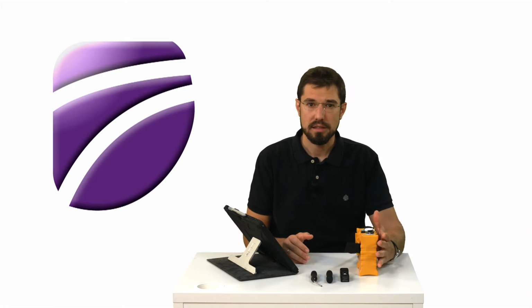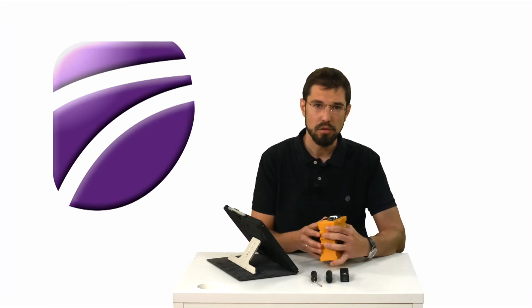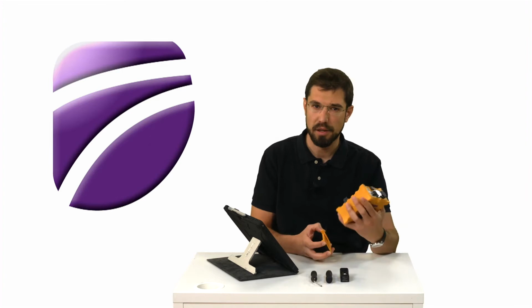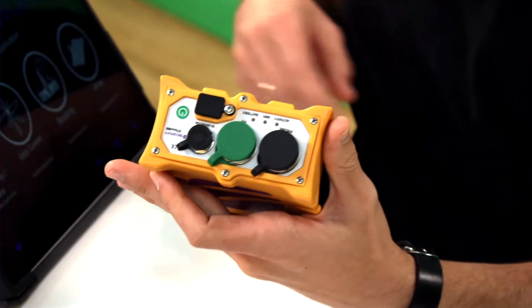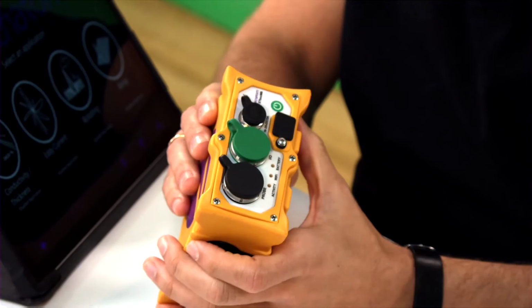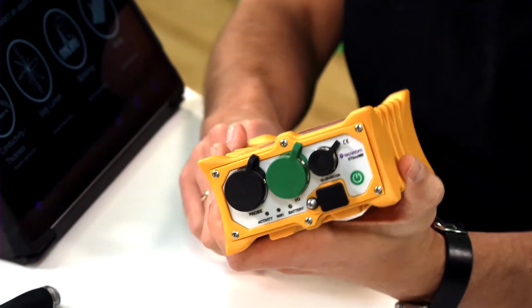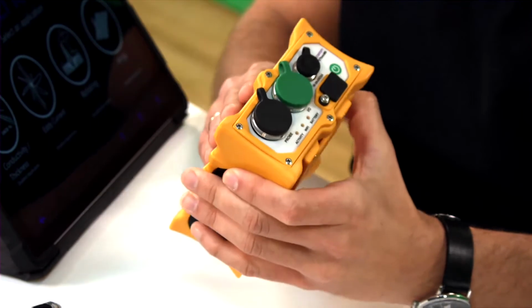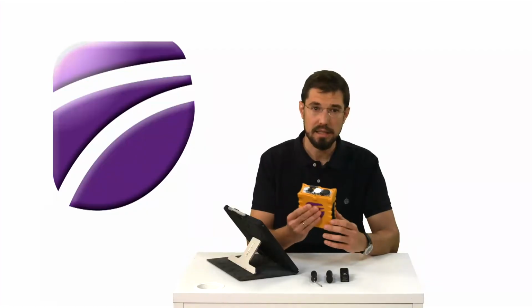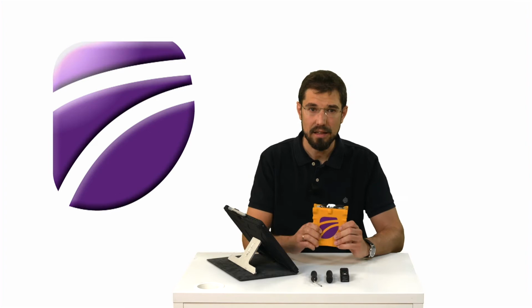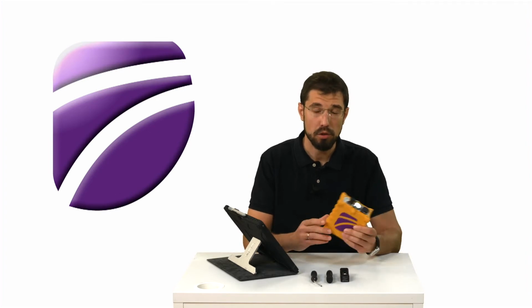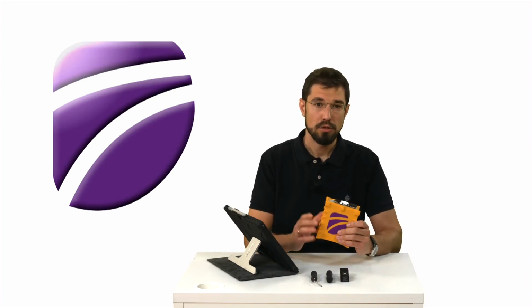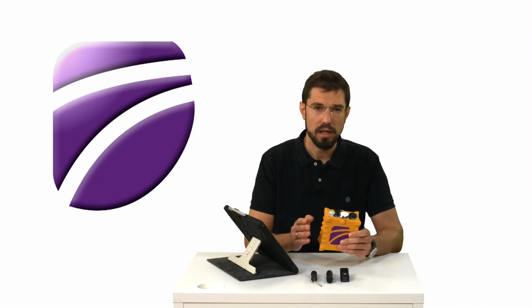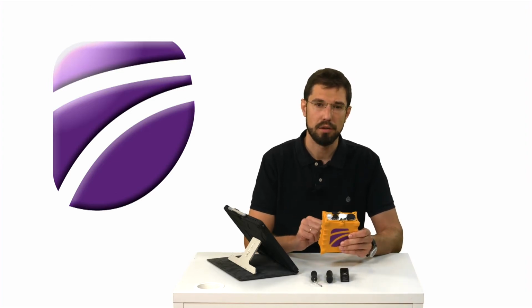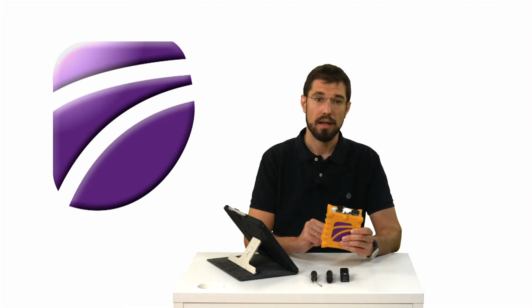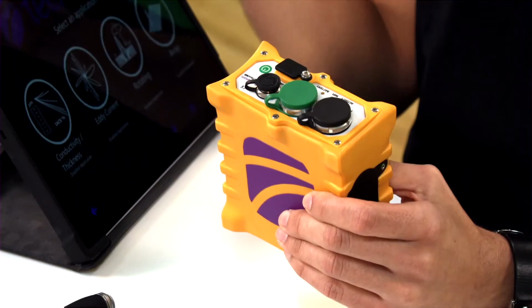As we can see, the ETboxMB is small enough to be transported easily to any inspection area, and powerful enough to act as a desktop in laboratories. It weighs around 700 grams, has a robust box that's resistant to falls and watertight, which means it's sealed against liquid splashes and can be operated in the rain, for instance. This is a multi-channel equipment that allows us to acquire up to 4 frequencies for the detection of indications, and whose range goes from 10 Hz to 10 MHz.